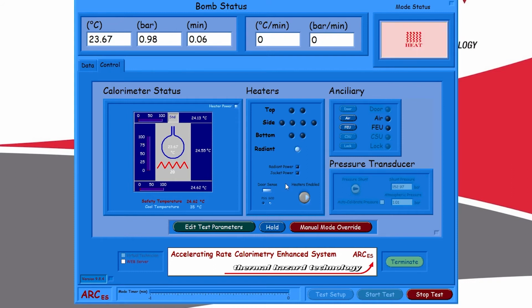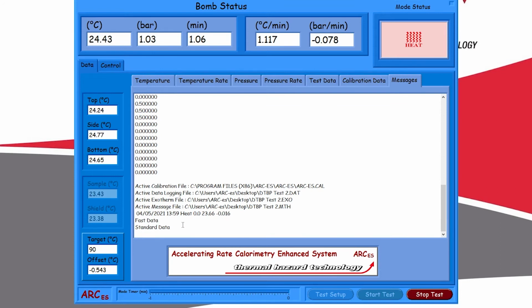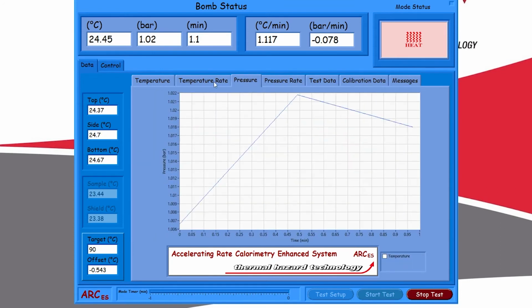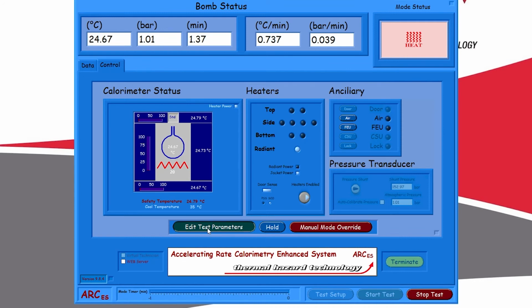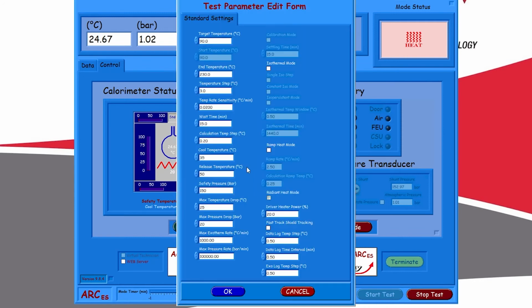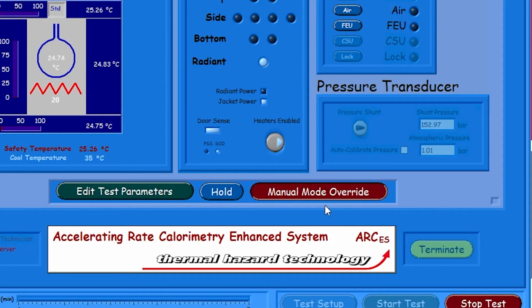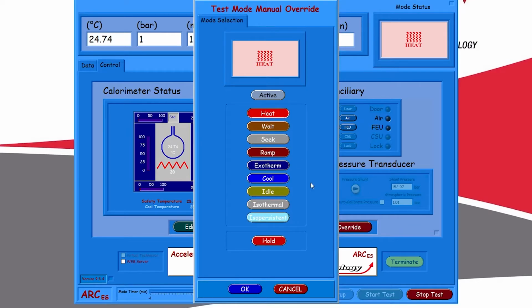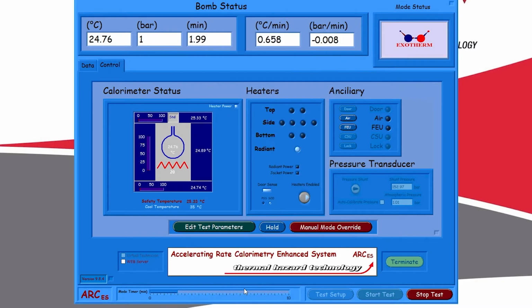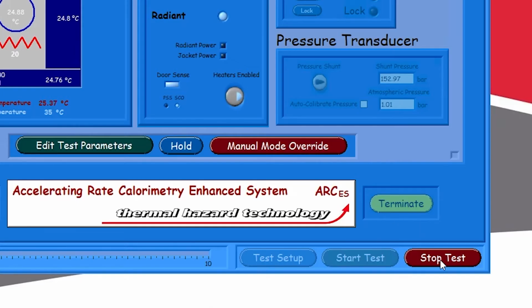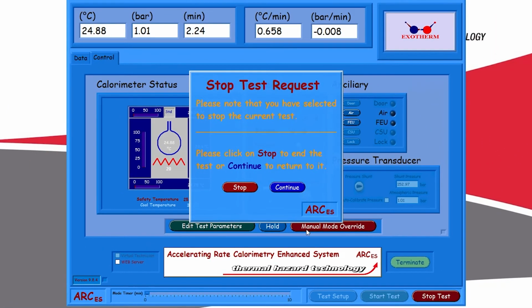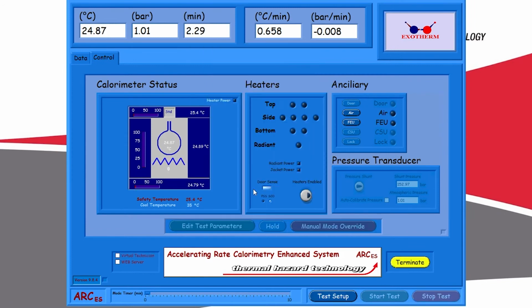In the Control tab, the lights indicating the calorimeter heaters will flash to show which heaters are operating. Back in the Data tab, the graphs are updated as data is collected. The Edit Test Parameters button can be used to change test setting during the test. The instrument operating mode can be changed using the Manual Mode Override button. The Stop Test button will stop all data collection and switch the instrument to cooling mode if the calorimeter has heated up.